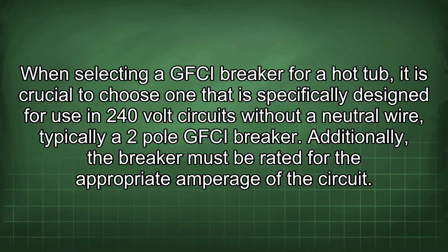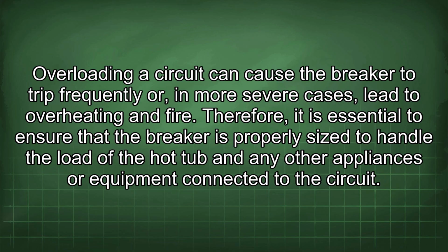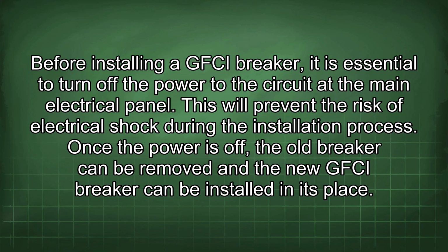Additionally, the breaker must be rated for the appropriate amperage of the circuit. Overloading a circuit can cause the breaker to trip frequently or, in more severe cases, lead to overheating and fire. Therefore, it is essential to ensure that the breaker is properly sized to handle the load of the hot tub and any other appliances or equipment connected to the circuit. Before installing a GFCI breaker, it is essential to turn off the power to the circuit at the main electrical panel. This will prevent the risk of electrical shock during the installation process.